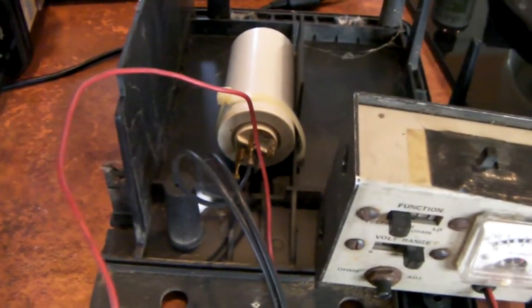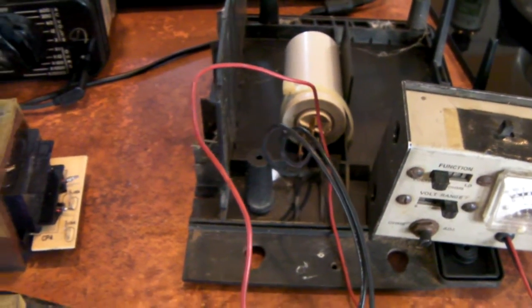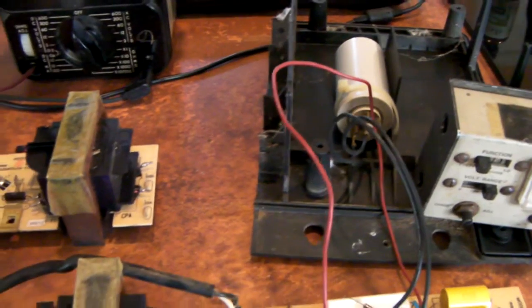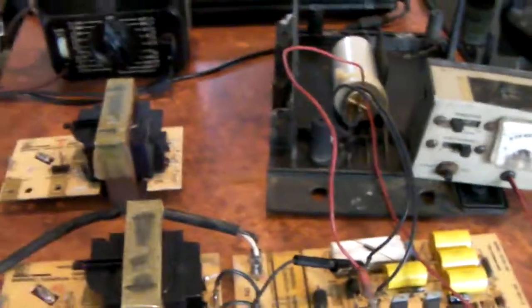And that's the capacitor. So even when you unplug this thing, that's charged to like 500 volts. That'll kick you right on your butt. Make sure you discharge that before you work on it. When I unplug this, that'll still be charged at 500 volts.